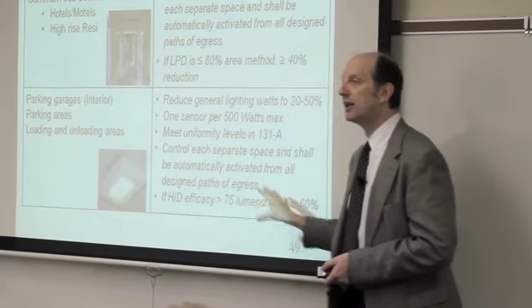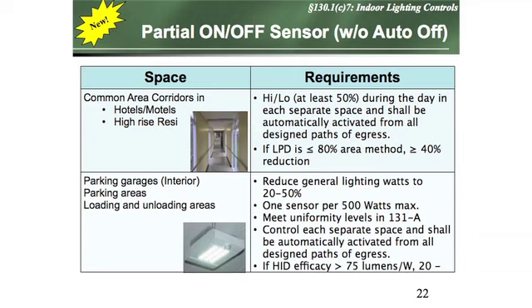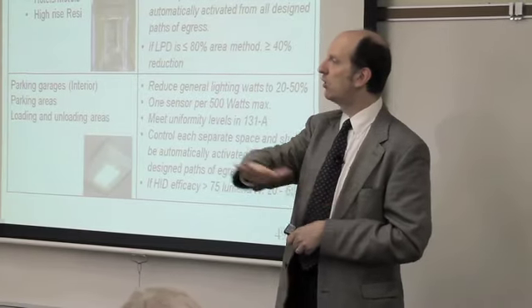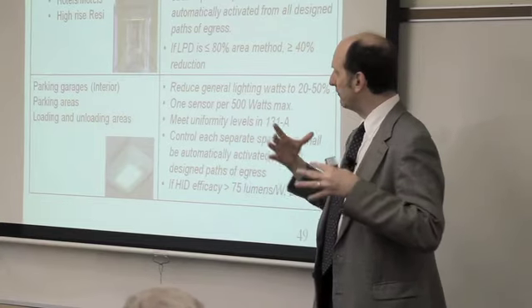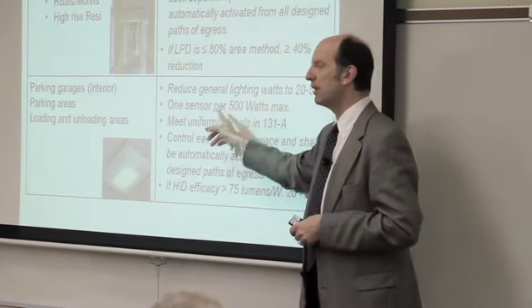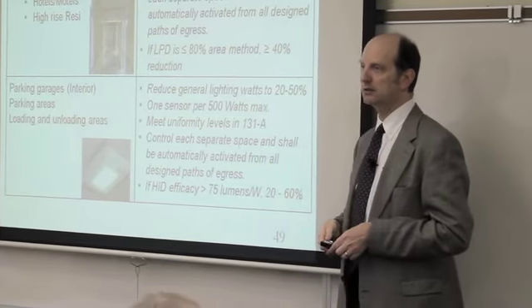And then here, parking garages used to be completely exempt from automatic off. So they're saying, okay, we're not going to tell you that you have to turn these off completely, right? This doesn't have an automatic off at the end of the day. But we want them set up so that they're high-low during the day, high-low during the night. And by the way, we also want to make sure that you don't have it so when you walk into one area of the garage, the whole garage goes on. Basically, if I walk into an area, I can't light more than 500 watts of lighting in the garage.